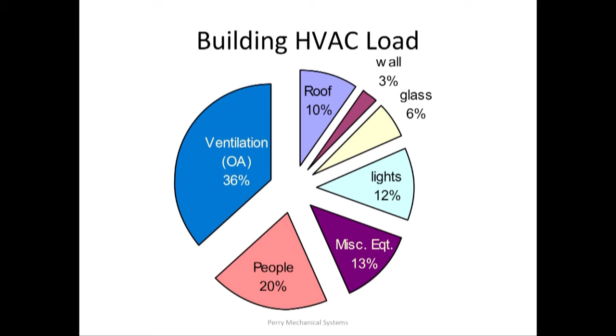So on the HVAC load here, we're looking at it again with some better glass in here. So our pie is changing a little bit as we go along. And as you can see, the biggest part still here is the ventilation. So how do we address ventilation? The code for ventilation is in ASHRAE as well. It's ASHRAE 62.1. And on a typical classroom, you're looking at about 13 to 15 CFM per person. They've revamped the code. It's not just a flat CFM per person anymore. It has to do with the square footage of the space as well.